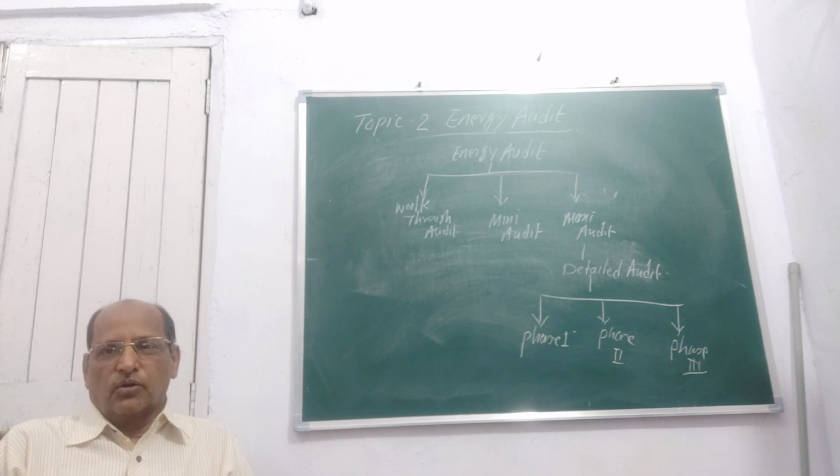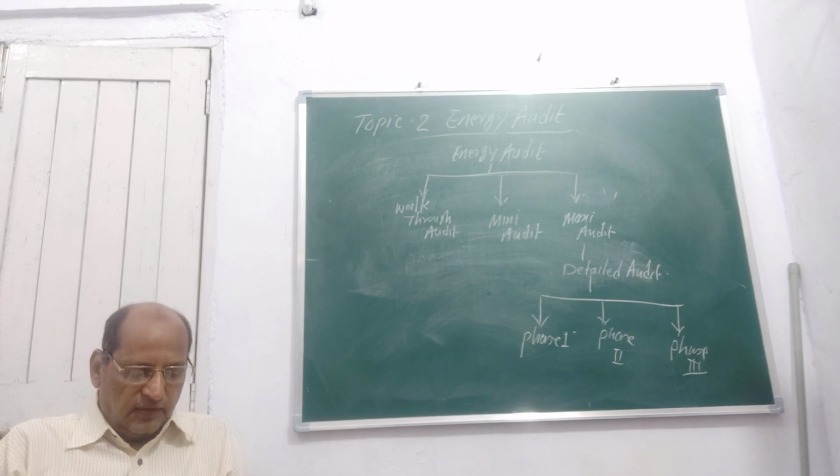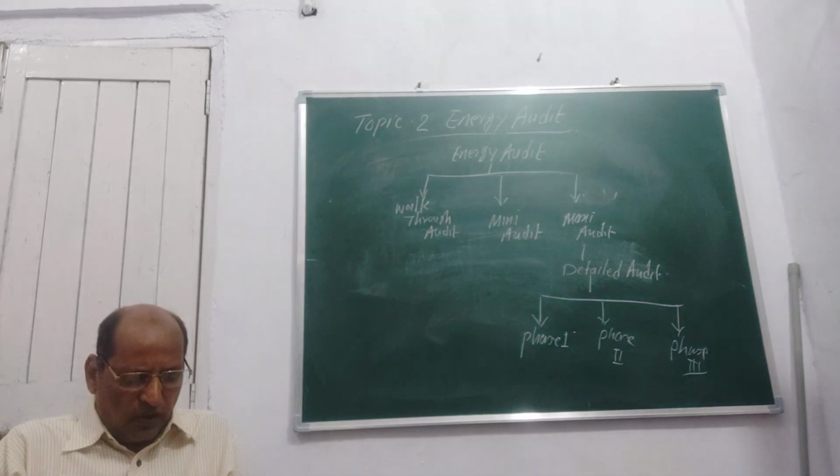So we have to work out the loading capacity of the machines and the time of loading of the machine, where we have to calculate the on period of the machine, and according to that, what is the efficiency of the machine, how much output it is giving, and according to that we calculate what the corresponding energy consumption is. So in preliminary audits there are certain points that you have to write.